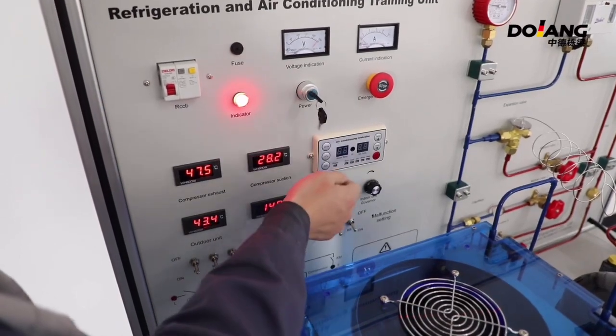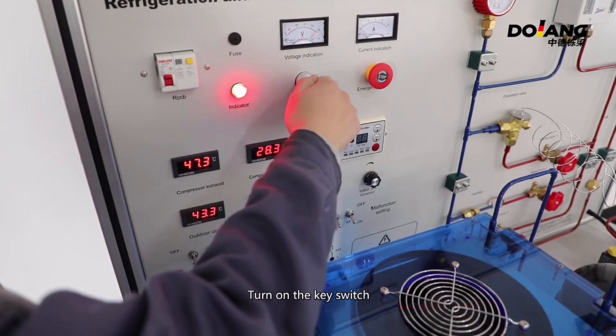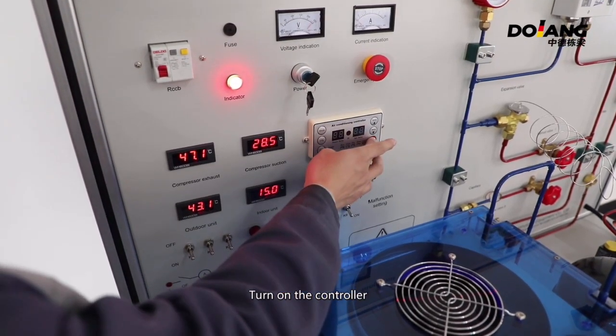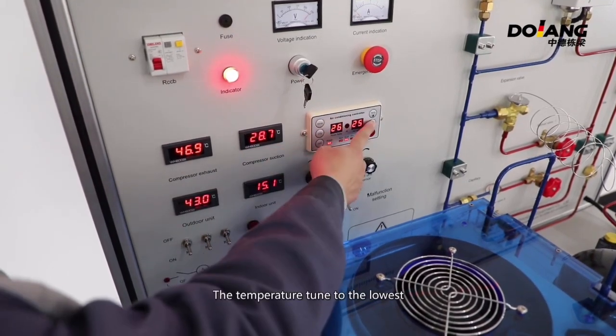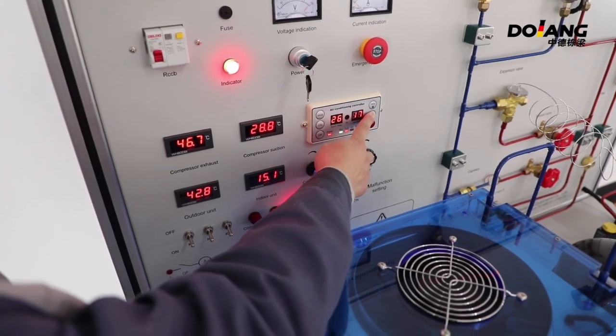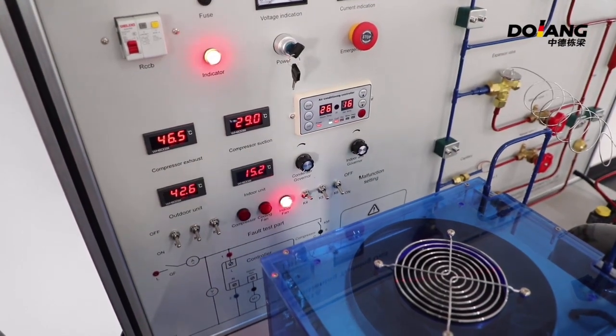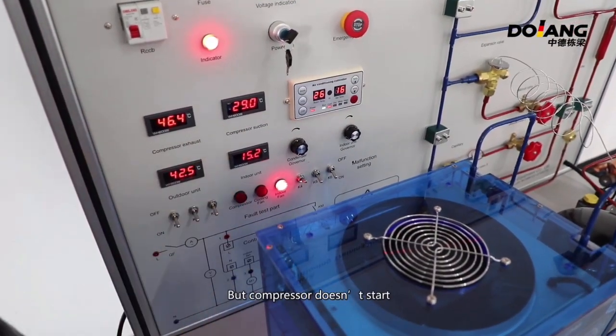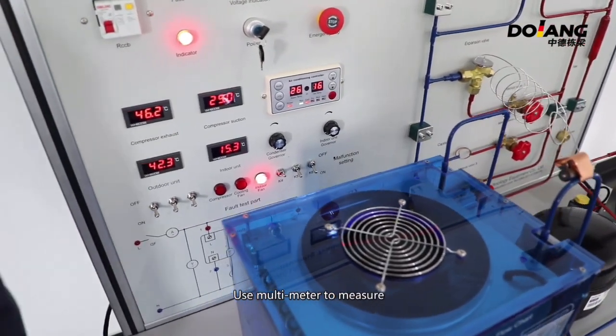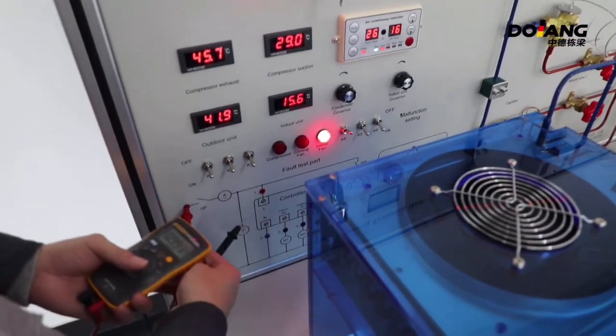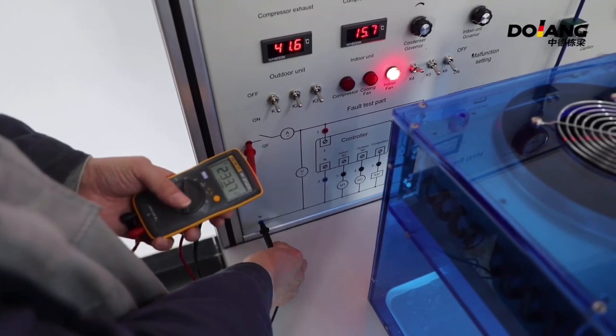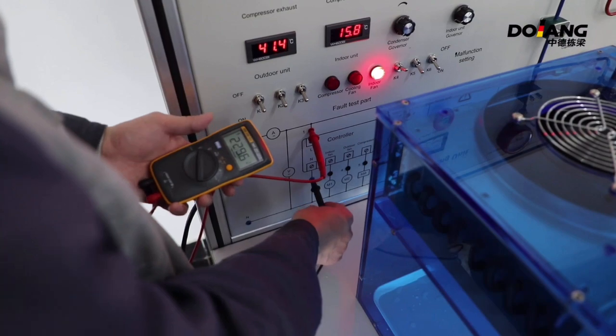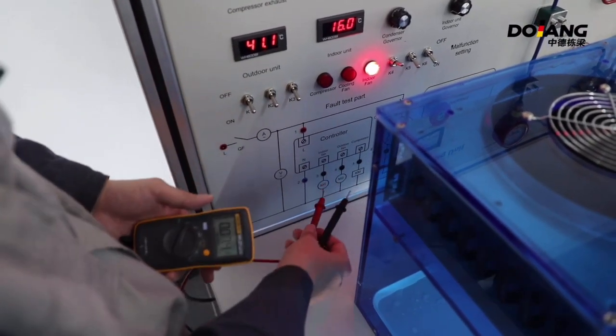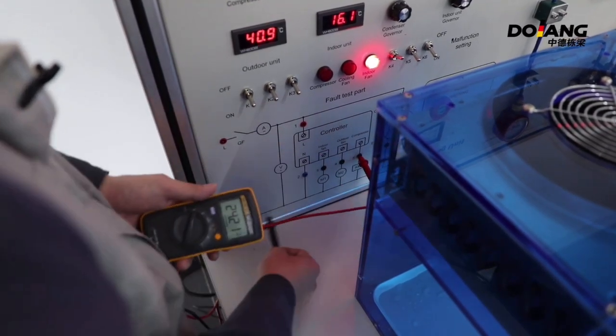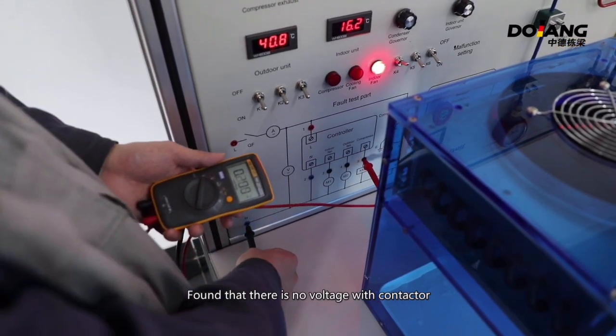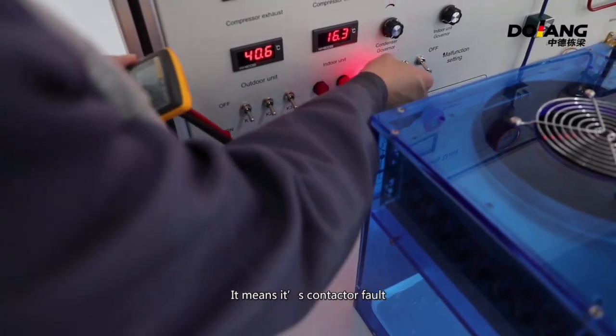Now do the fourth fault experiment. Turn on the circuit breaker. Turn K4 to off. Turn on the key switch. Turn on the controller. Mode turn to cooling state. Now temperature turn to the lowest. Now fan runs. Indicator is on, but compressor doesn't start. Use multimeter to measure. Found that there is no voltage at the contactor. It means it's a contactor fault.